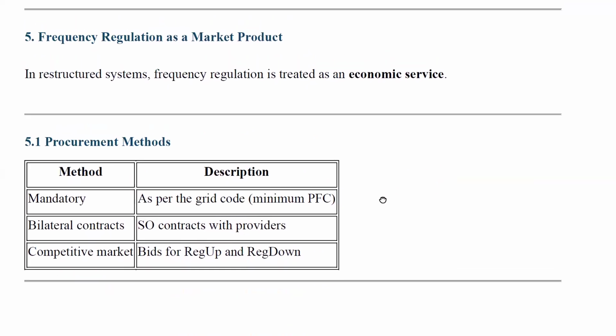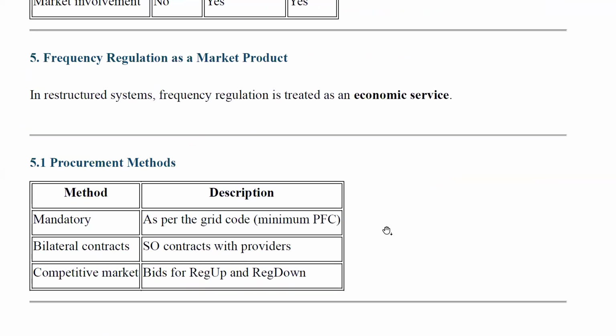Next comes frequency regulation as a market product. In a restructured system, frequency regulation is treated as an economic service. If you take the procurement methods of this service, it is mandatory as per the grid code, so that minimum PFCs are maintained. Next comes the bilateral contract, where the system operator contracts with the providers. Next, competitive market, with bids for regulation up and regulation down. So these are the procurement methods for frequency control.